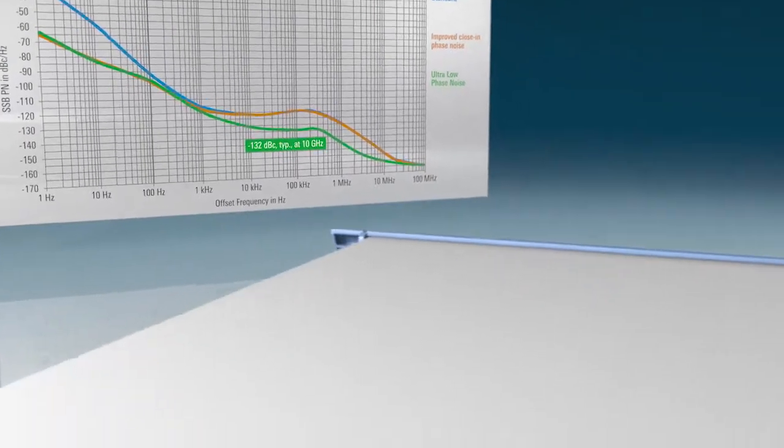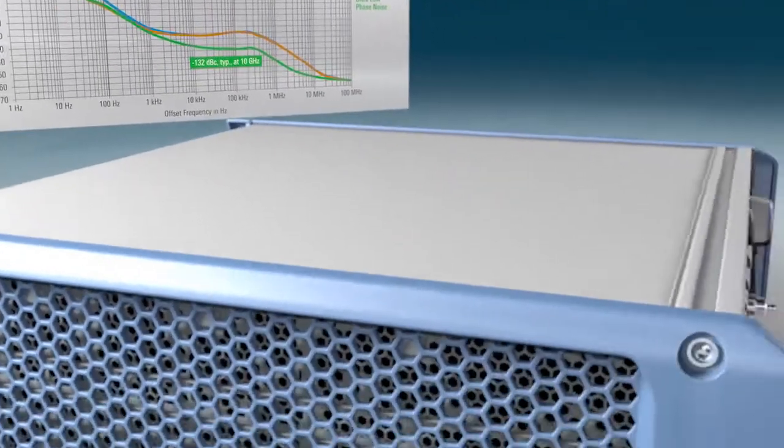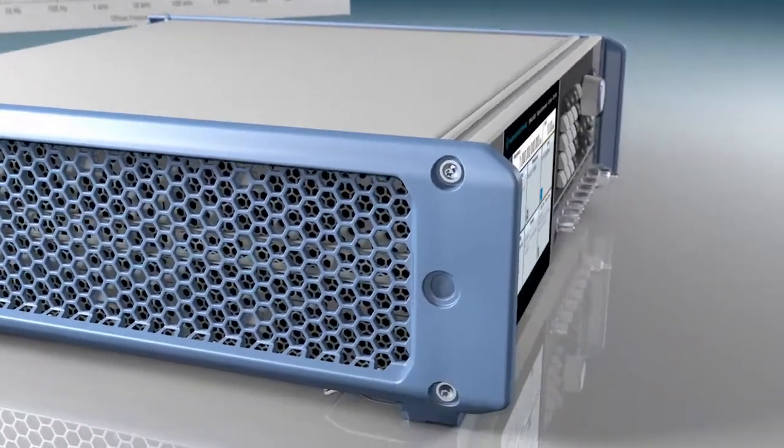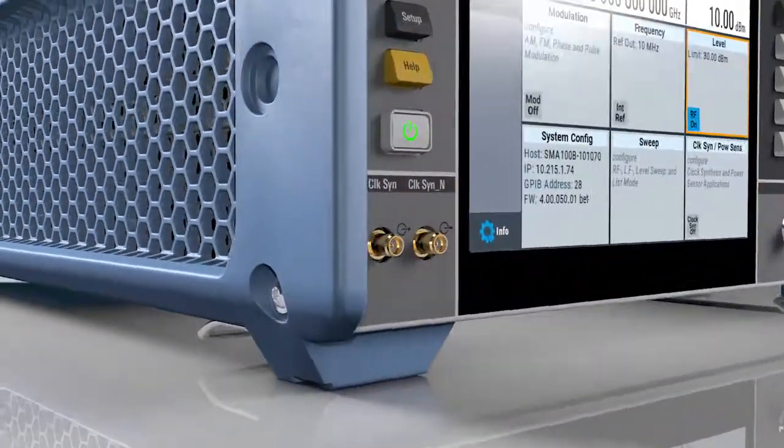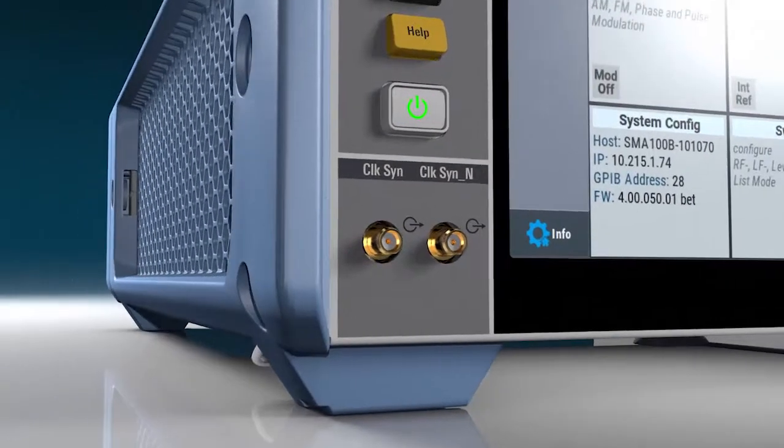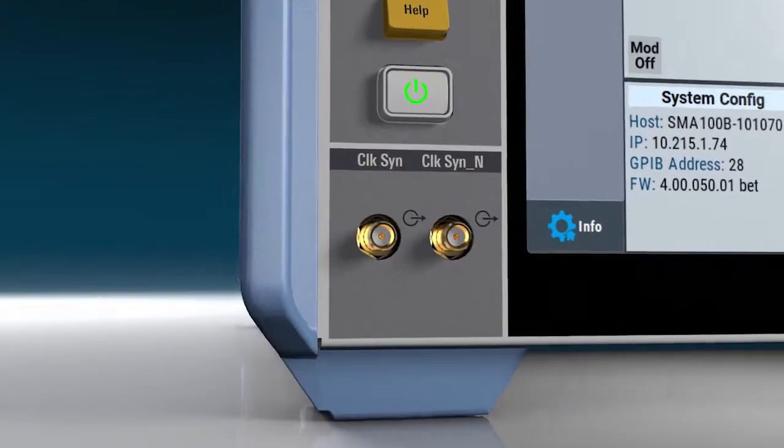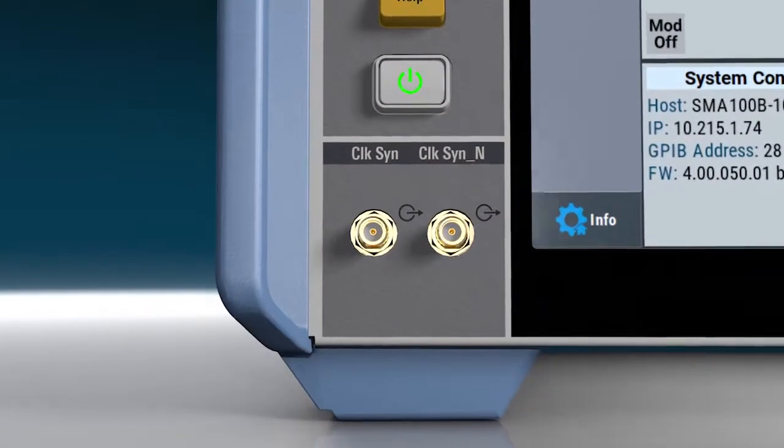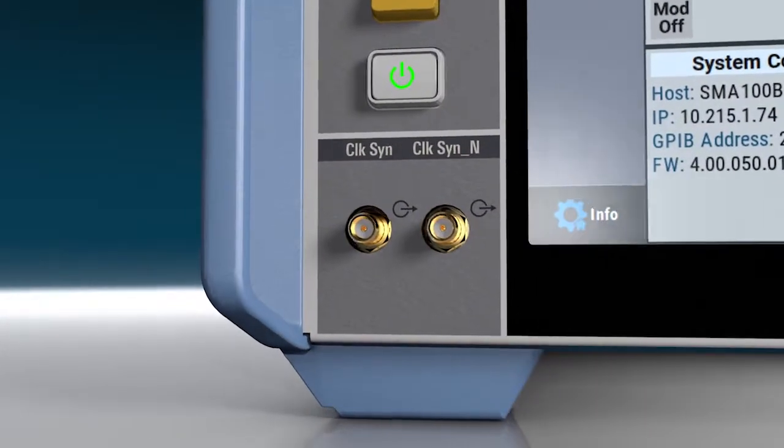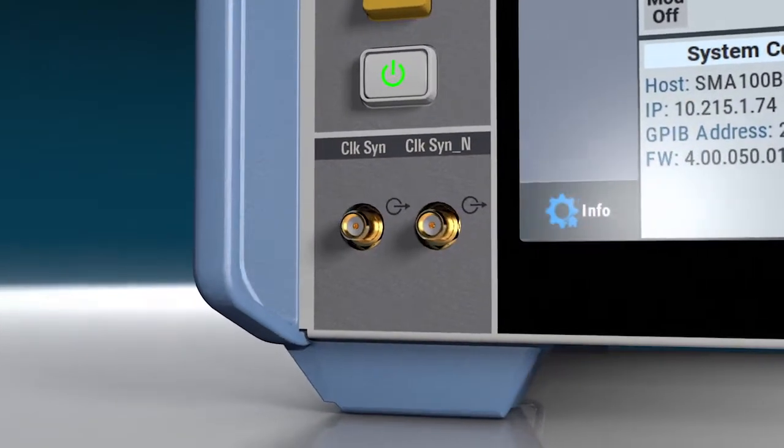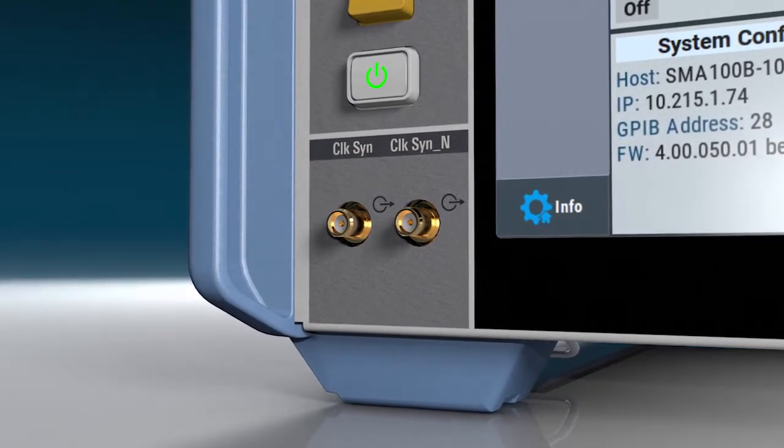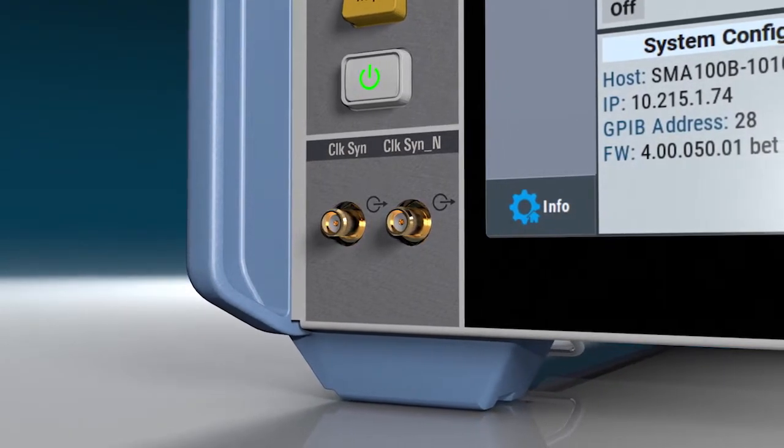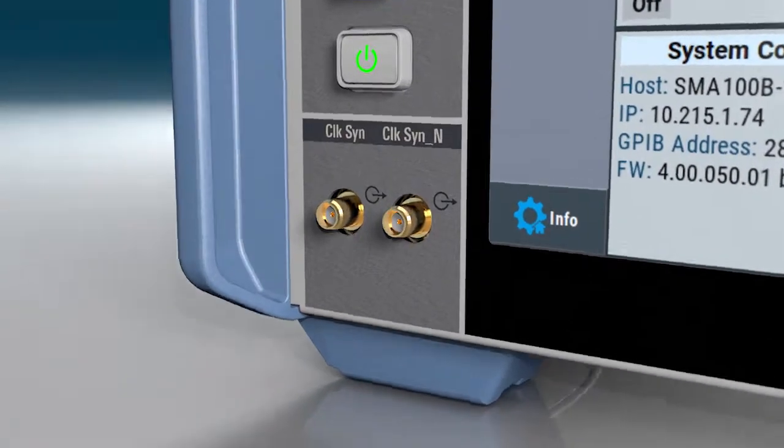The SMA100B offers two additional outputs. At the clock output port, it provides a second independent signal for analog-to-digital converters. This signal features even lower wide-band phase noise than the RF output signal.